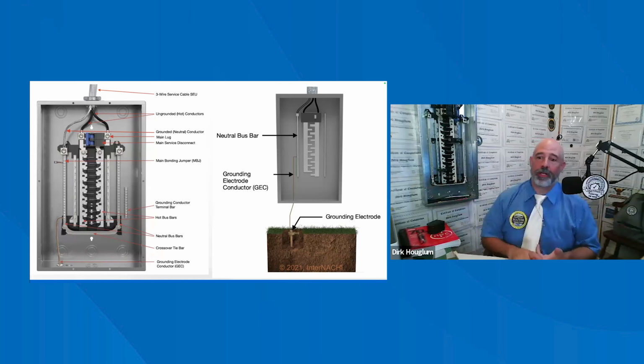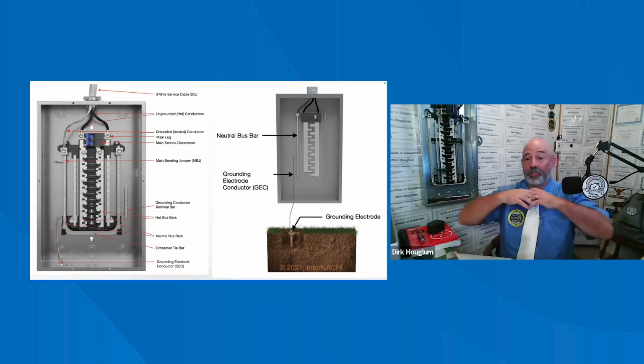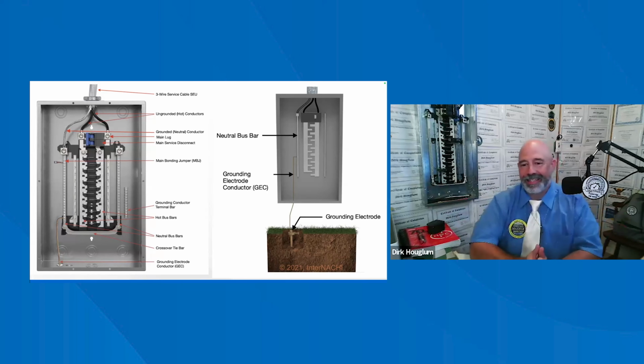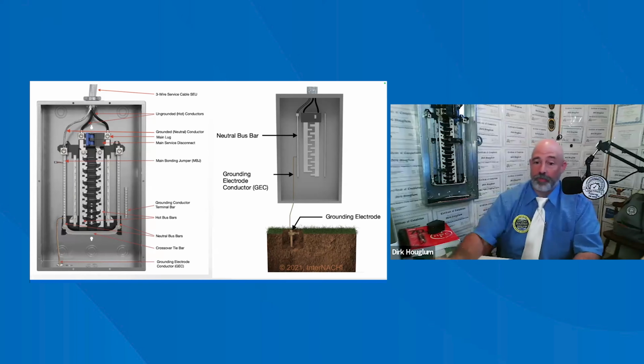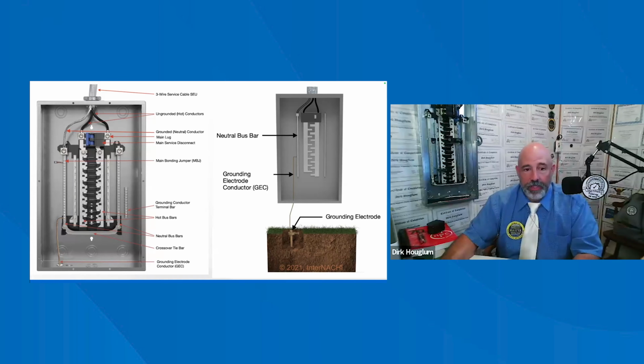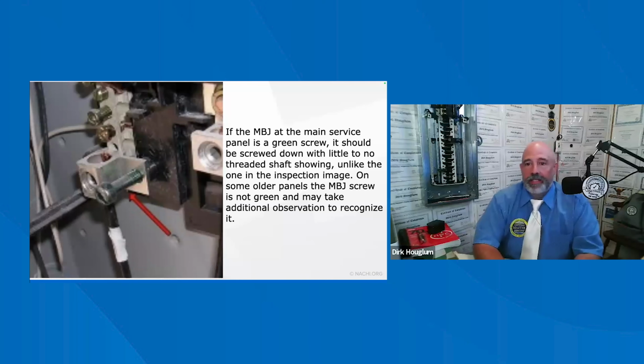In this setup, the neutral bus bar acts as the main bonding jumper because it ties the neutral and the ground systems together. They're symbionts. Inside the main service panel, all the ground wires attach to the grounding bar, which is bonded to the main cabinet through the MBJ. So from the same grounding bar, a large bare or green wire, the grounding electrode conductor, the GEC, runs out and connects to the grounding electrode. That could be the ground rod driven or the Ufer or whatever it is, or the 20-foot section of rebar. Okay, so hope y'all are getting this. At the main disconnect, all neutrals and grounding wires are combined and connected.